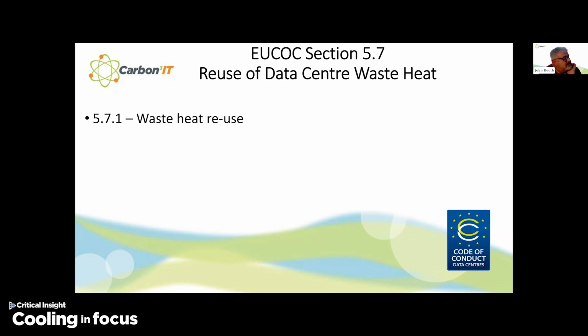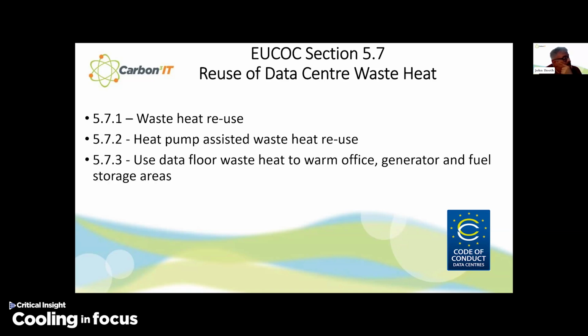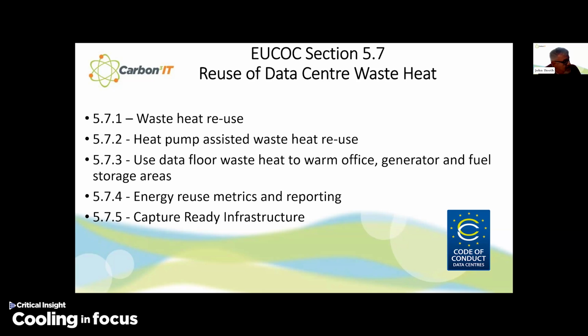And then for the reuse of data center waste heat, there's waste heat reuse, so kind of formulating that you should be using your waste heat. Then heat pump assisted waste heat reuse, and use your data center waste heat within your system boundary to warm your office, generator, or fuel storage areas. Consider the energy reuse metrics and reporting, which are now part of the Energy Efficiency Directive. And then think about capture-ready infrastructure. So this is basically to make sure that you extend your cooling loop to the perimeter of your buildings so as to be able to connect to an existing or a future district heating network.